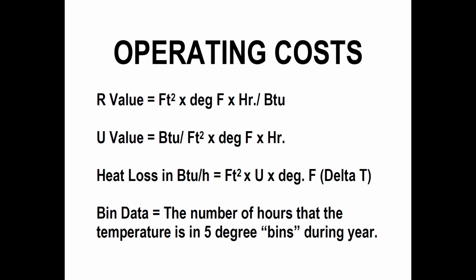I think I'm going to digress a little bit on this. So the heat loss calculation is, if you have that wall right there, it's got a certain amount of insulation behind the sheetrock. It's got a certain amount of insulation value to the windows. And we calculate what the heat loss is out of all these surfaces that are exposed to the outside through this formula to come out with what the BTUs are required. So the room that you have, wherever you've got the heat pump, who knows whether anybody did the calculation. They said, it should be about this. Okay. I'm going to leave that for the bin data for a moment.